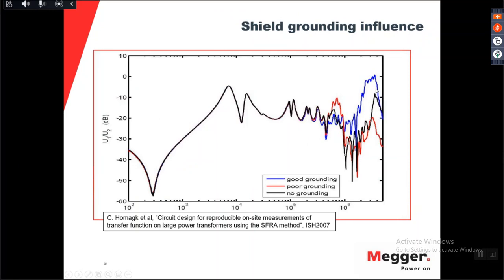Now, if you look at the actual standard, it says you should measure to 2 megahertz. Now, the test equipment from Megger goes to 20 megahertz, which is completely useless. Above the 2 megahertz, you will only see how you have connected poorly or something like that. So you have no benefit at all in going to higher frequencies. That's a very, very quick run-through of the SFRA measurement.